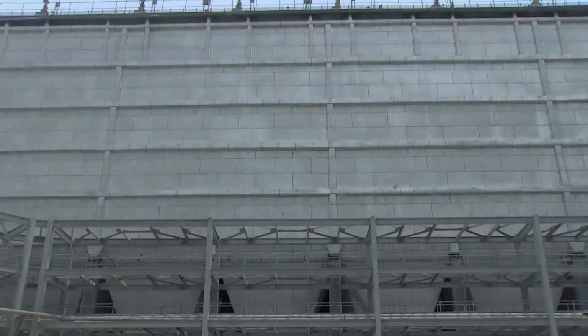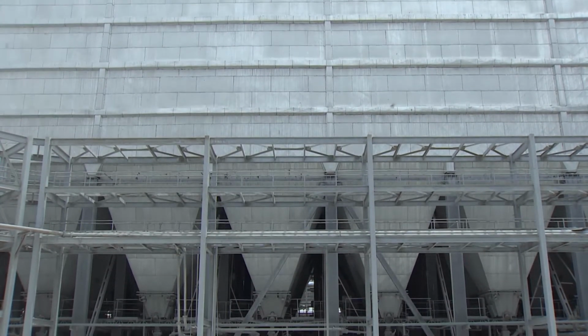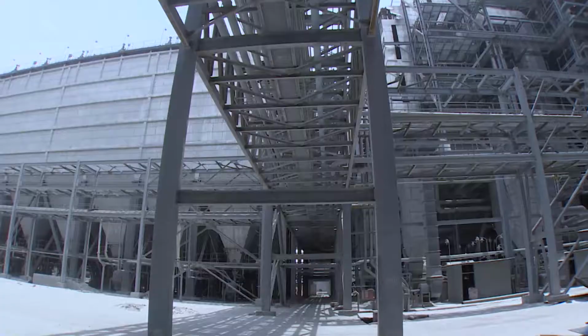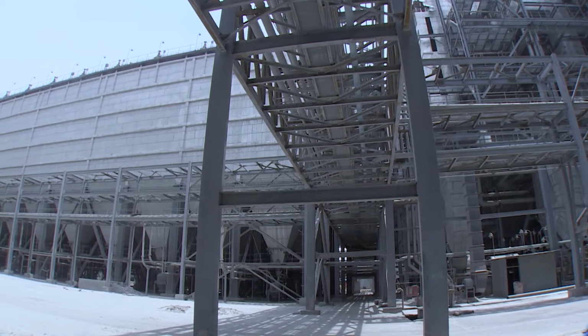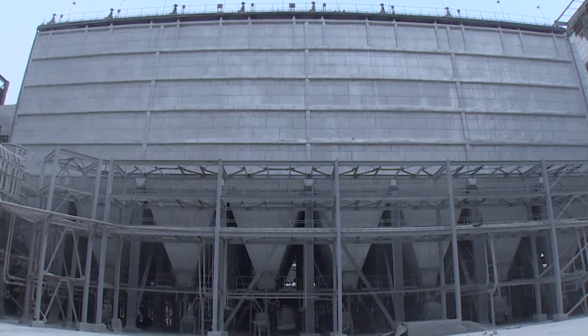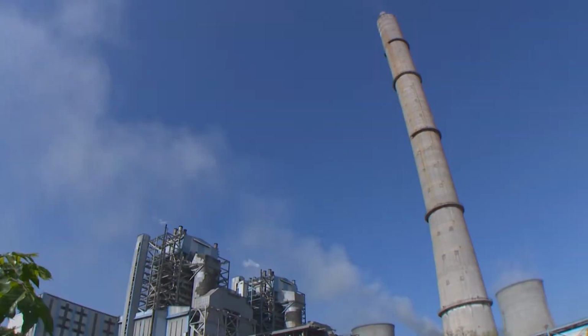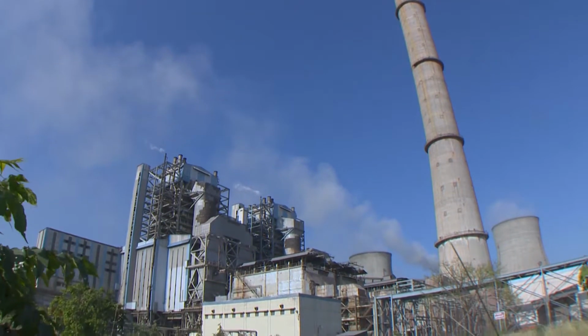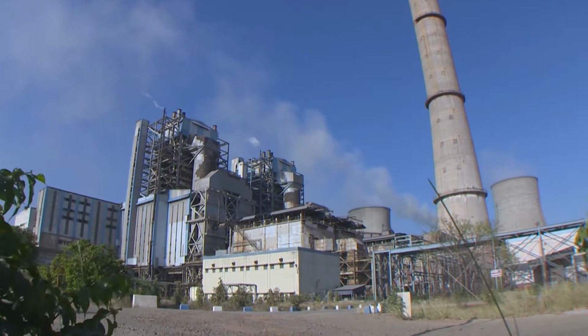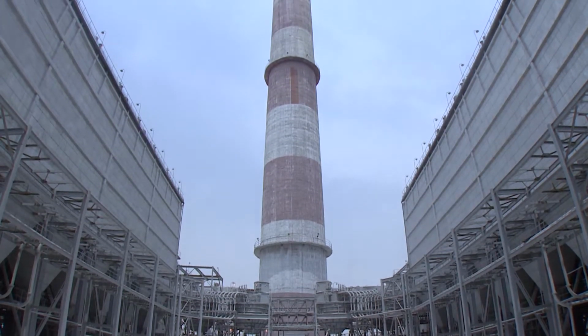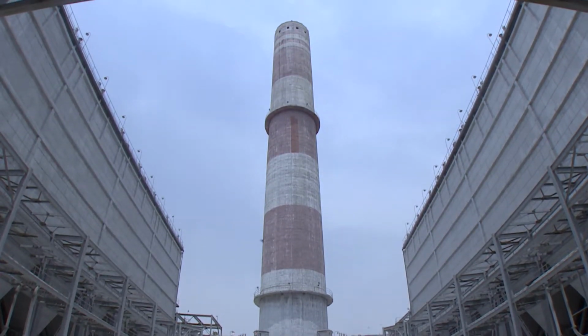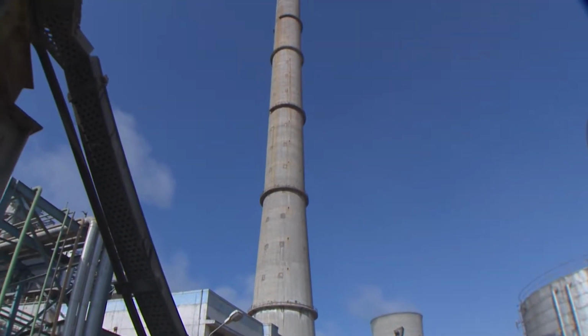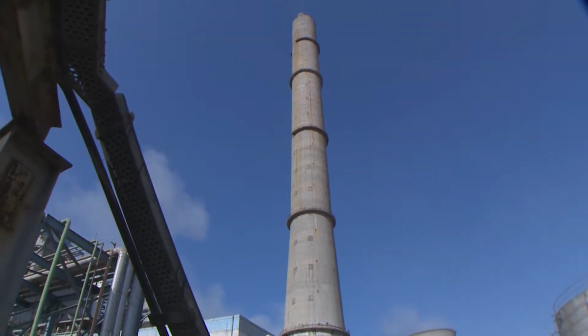Electrostatic precipitator. The electrostatic precipitator removes the fly ash from the flue gas so that the suspended particulate matter at the stack outlet is maintained within acceptable level. Chimney. The dust-free flue gas is discharged to the atmosphere by the ID fan through the chimney. The height of the chimney helps proper dispersion of flue gas into the atmosphere, thereby reducing ground level concentration of pollutants.